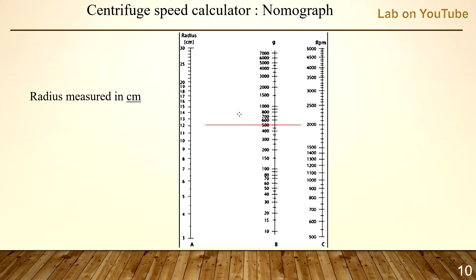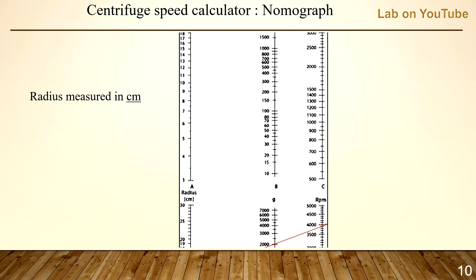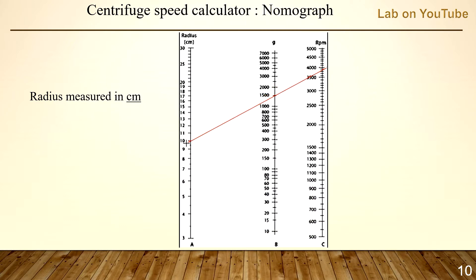This is a nomograph chart. All you need is to plot your numbers, place your ruler at the right radius and selected RCF, then read the RPM for your centrifuge. As you can see, the smaller the radius, the higher the RPM required to achieve the same RCF. I'll put the link for this chart below the video as well.